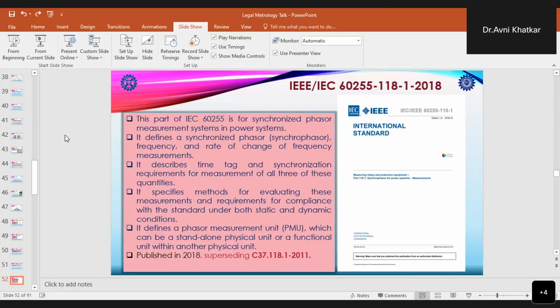Now, this is the most current and prevalent standard for PMUs, and it is part of the IEC 60255 standard, for synchronized phasor measurement systems in the power system. This international standard defines a synchronized phasor, that is synchrophasor, and frequency and rate of change of frequency measurements. It also describes the time tag and synchronization requirements for measurement of all three of these quantities, and it specifies the methods required for evaluating these measurements and the requirements for compliance with the standard under both static and dynamic conditions. It also defines a phasor measurement unit, that is PMU, which can be a standalone physical unit or a functional unit within another physical unit.